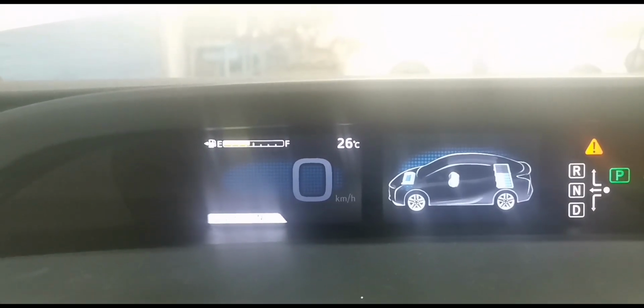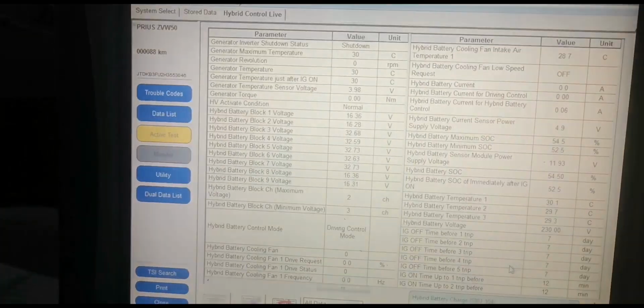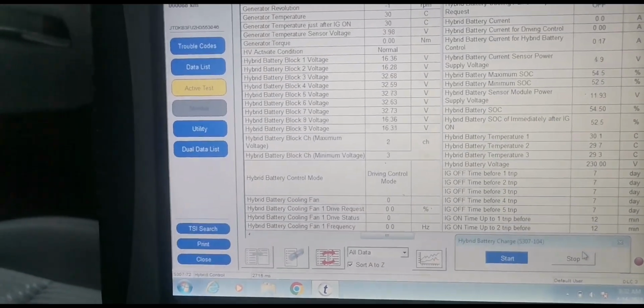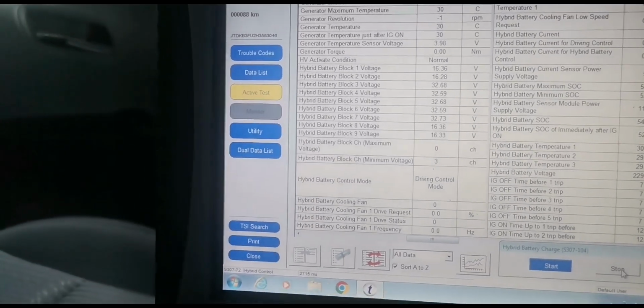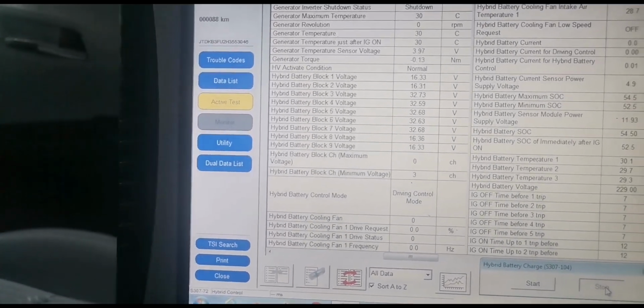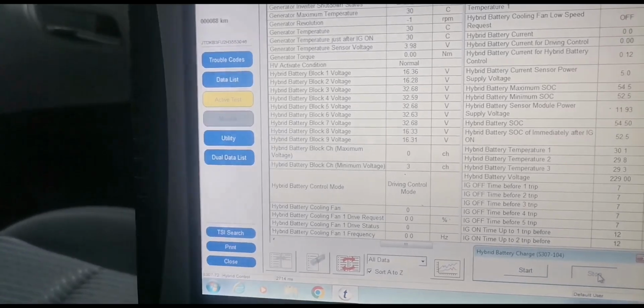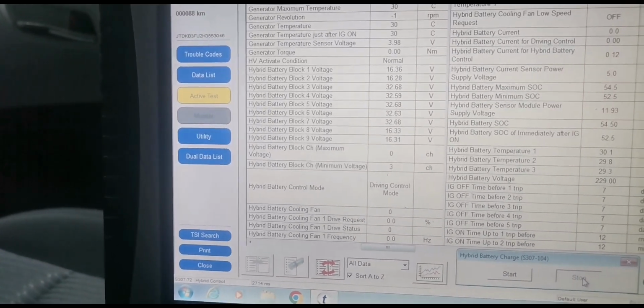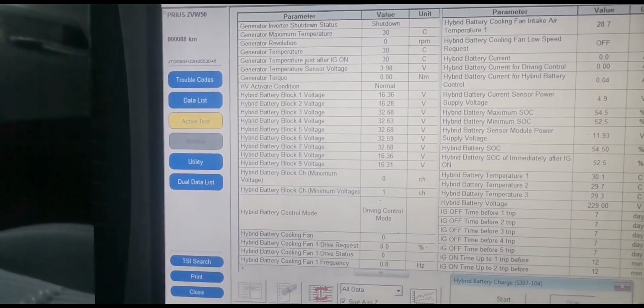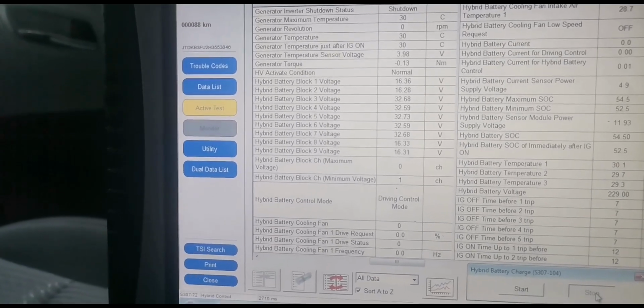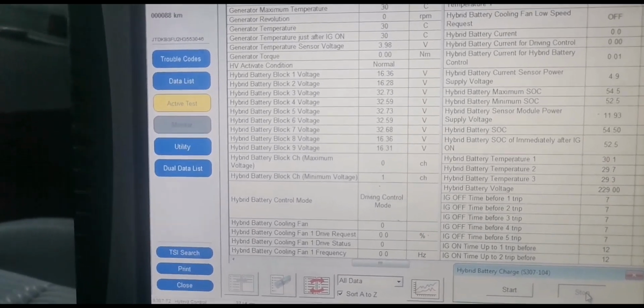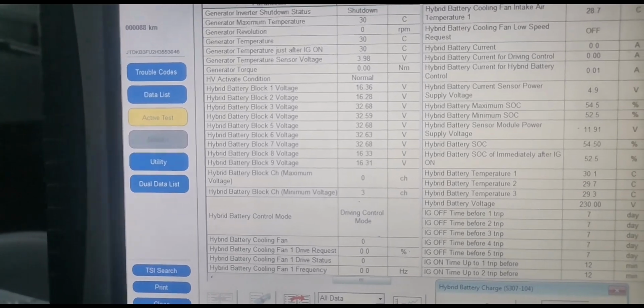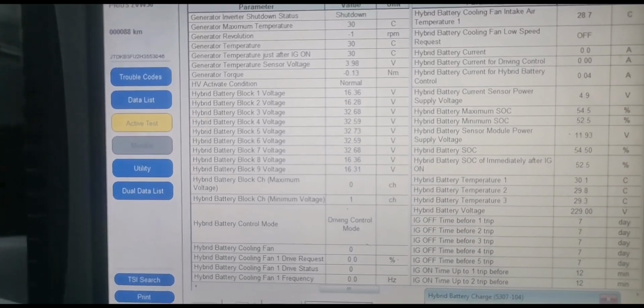So all you have to do now is deactivate: stop and disconnect the main relay. The next thing we will do is remove the service plug grip, remove the negative battery terminal, or do the procedures for disabling or shutting down the high voltage circuit, and return all the original connections on the system.